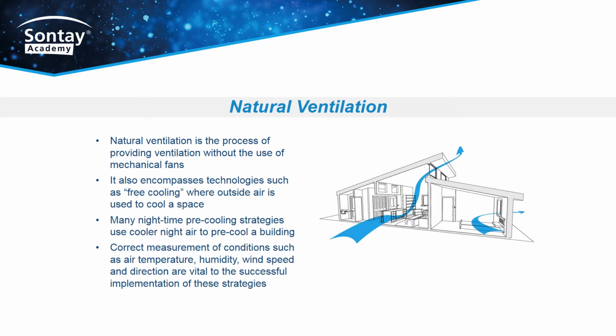automating the process will help maximise the benefits of natural vent schemes, whilst maintaining comfortable internal conditions. Strategies utilising natural ventilation need to have input on air temperatures, wind speed and direction in order to provision this functionality. Nighttime pre-cooling routines need accurate information on many parameters to ensure pre-cooling is provisioned with no detrimental effects, such as condensation forming on the conditioned space.